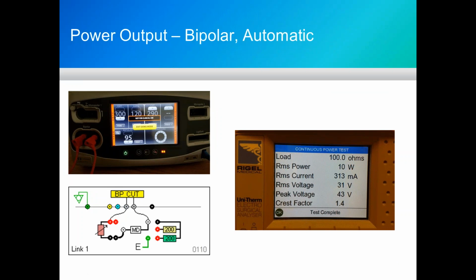So next we're going to demonstrate doing a bipolar test. You'll see that I have 2 jacks, or 2 leads, coming out of the FT10 on the bipolar portion. We don't use patient return monitoring in bipolar. And there is the schematic diagram, bottom left, as to how we'll make our connections to the side of the Unitherm.